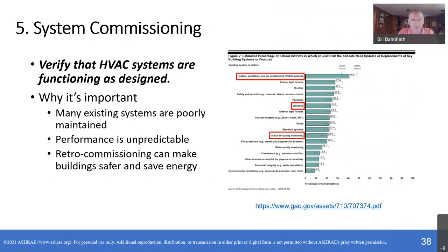And then finally, system commissioning. It's very important that systems be checked to make sure that they're operating up to their design intent. We know that many systems are poorly maintained, and so we really don't know what level of protection they're providing under those circumstances. And also, it's well known that if we keep systems commissioned, we're likely to save energy as well. So this also works in the direction of the recommendation or the desire to save energy.